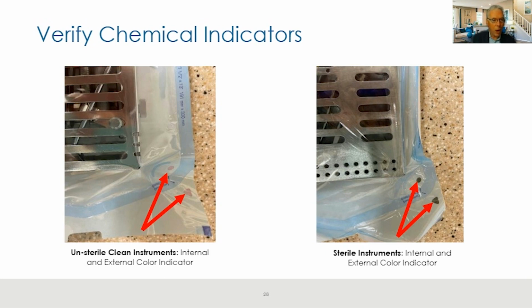This is part of what I call the triple check, which we teach at compliance training partners. Whoever takes instruments out of the autoclave is trained to check, for every package as they pull it out, that both indicators have turned black. Whoever then puts them into storage does not put the package into a drawer or cabinet until they've looked and confirmed it's turned black. Then the third part of the triple check: whoever takes those packages out to put them on the tray for the doctor or hygienist to use checks it again.